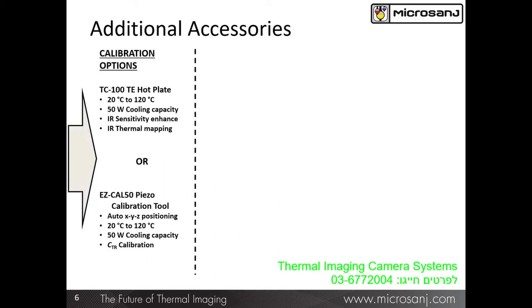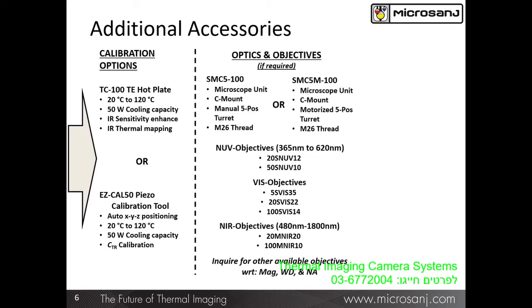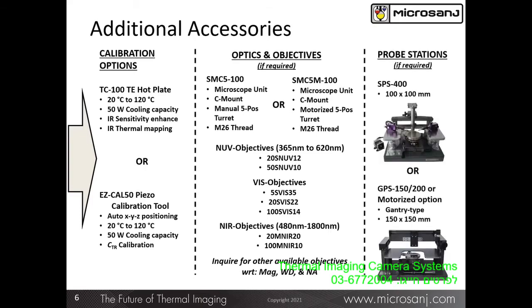Additional accessories include a TC100 thermoelectric controlled hot plate. This is a good accessory for infrared imaging. And the EasyCal 50 piezo calibration tool, which is an important accessory for thermal analysis of samples that have submicron features. I'll describe these 2 accessories in a little more detail on the next slide. And additionally, for customers that do not have or do not want to use existing in-house optics or probe stations, these can be provided by Microsanj as well. Manual 5-position or motorized 5-position optical head is available with a wide range of objectives, a few of which are shown here, with many more available with varied magnification, varied working distances, and varied numerical apertures. And we can also provide a probe station.